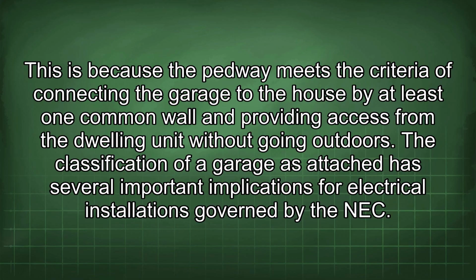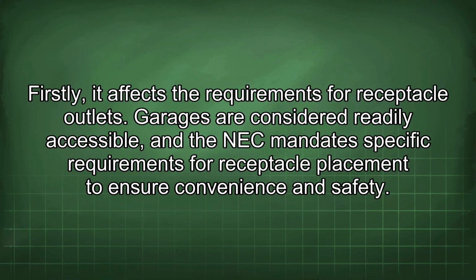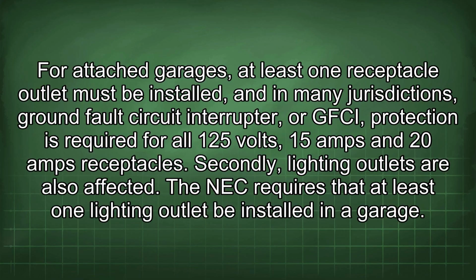The classification of a garage as attached has several important implications for electrical installations governed by the NEC. Firstly, it affects the requirements for receptacle outlets. Garages are considered readily accessible, and the NEC mandates specific requirements for receptacle placement to ensure convenience and safety. For attached garages, at least one receptacle outlet must be installed, and in many jurisdictions, ground fault circuit interrupter, or GFCI, protection is required for all 125 volts, 15 amps and 20 amps receptacles.